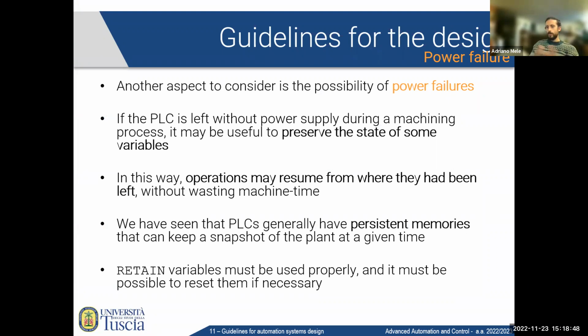Again, in that case, if you have this counting machine, you want to store the counting value so that if the power fails, you don't need to start counting from scratch, and you don't end up with a half full box that you need to throw away or fill manually before you can start. That's a simple example, but you get the idea. In general, the point here is to resume operations from where they were left off without wasting any machine time.